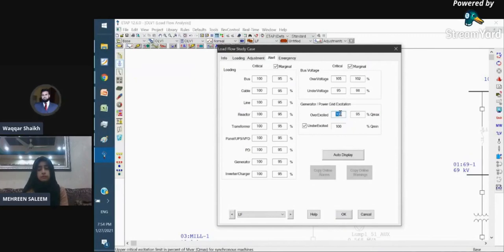If you have excess reactive power in the system, it will be absorbed by the generator, which may go into an underexcitation alert state, absorbing more and more reactive power. This is also a dangerous situation. So first, properly model the generator capability curve, then fine-tune the limits to respect during simulations, taking care of overexcitation, underexcitation, and overload conditions.